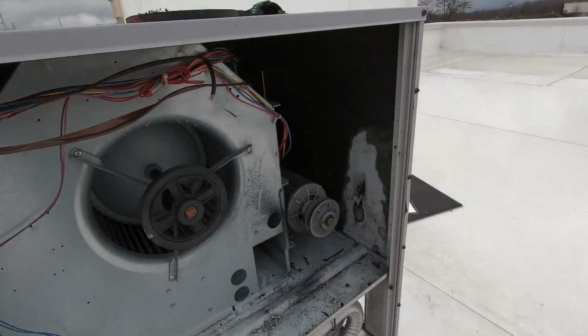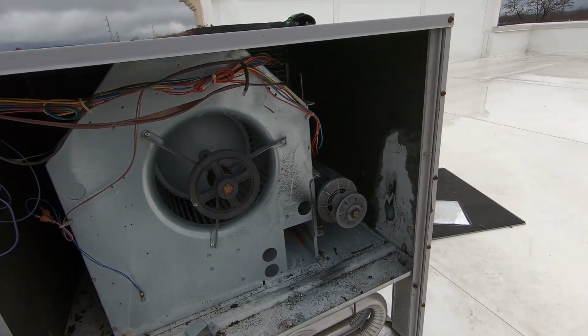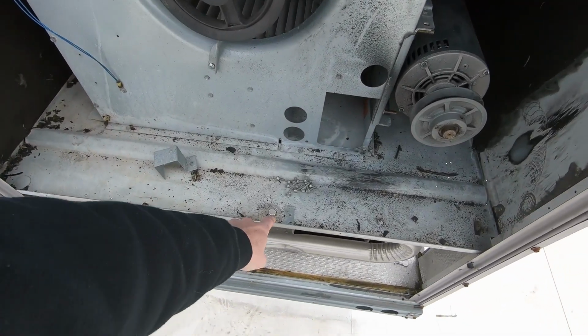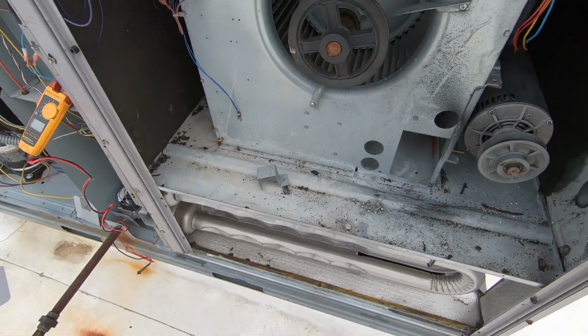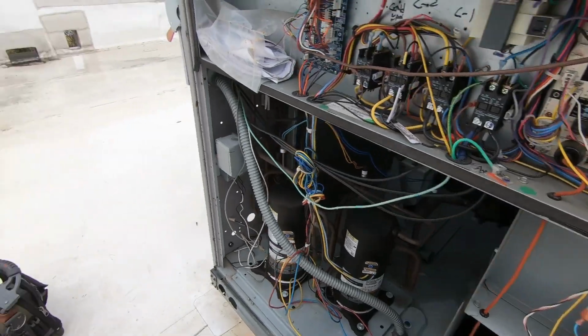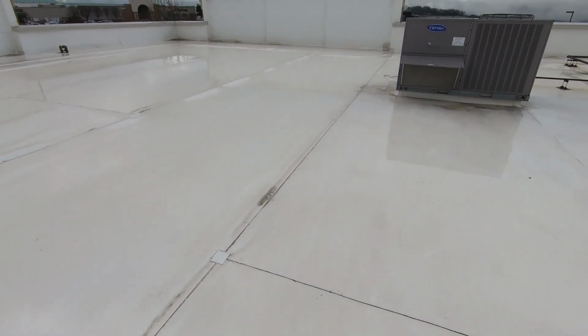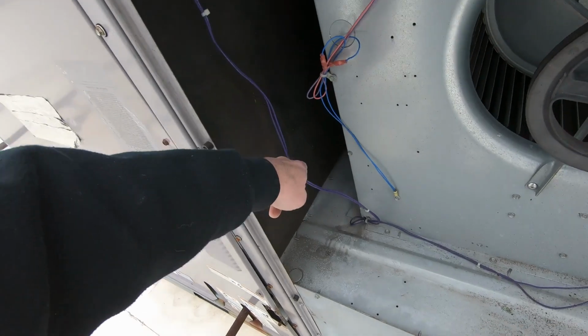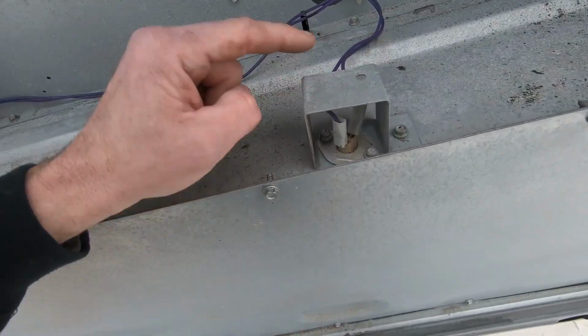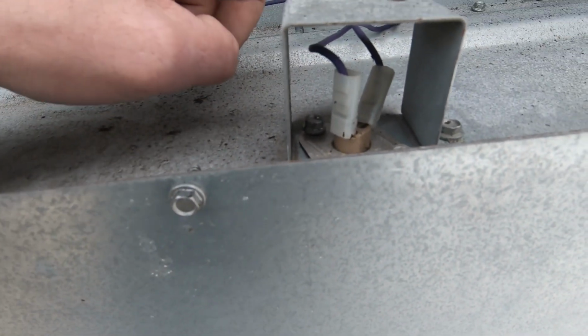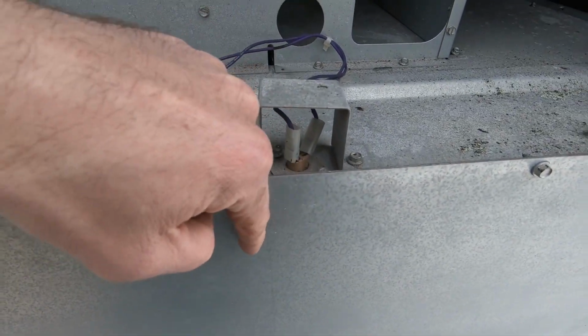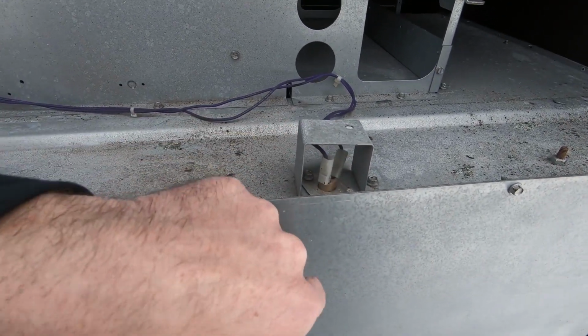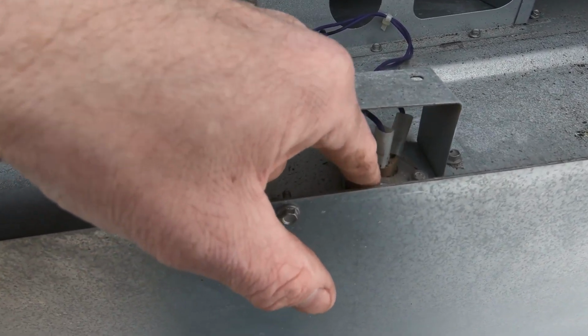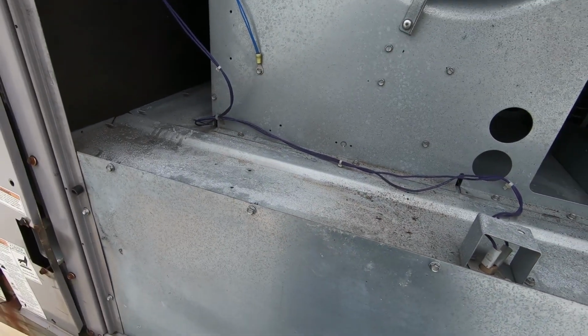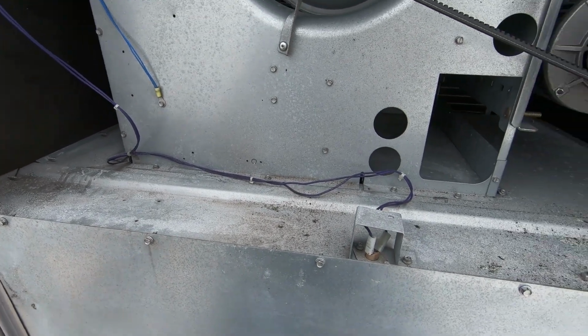So for that alone, I'm writing up the blower motor. I'm also writing up, we need a new limit and it needs to be wired in. Let me show you what a proper limit switch looks like on the other Carrier. This purple wire comes all the way down here, and the limit switch is upright with the sensing part of the switch down. So it senses the heat of the heat exchanger. And if it gets too hot, it opens this switch and shuts the gas off, you know, shuts the heat operation down to the unit.